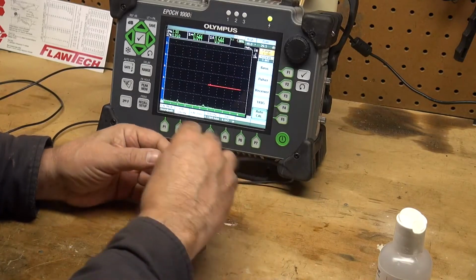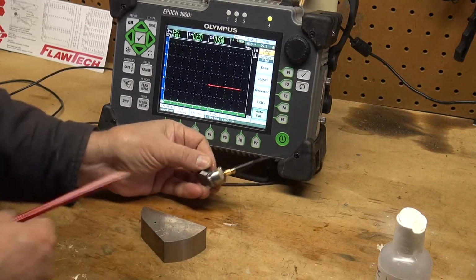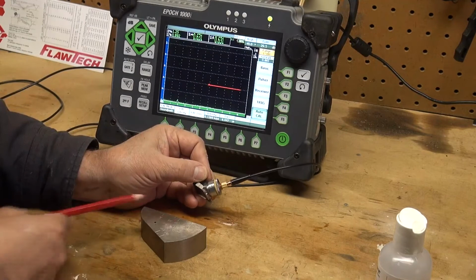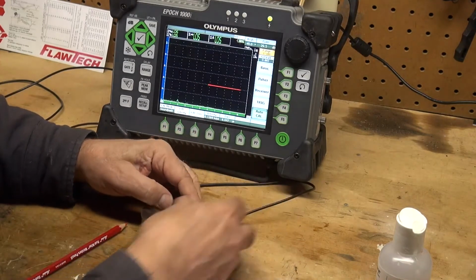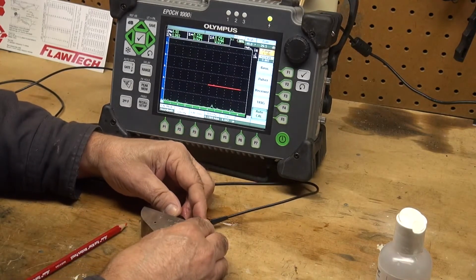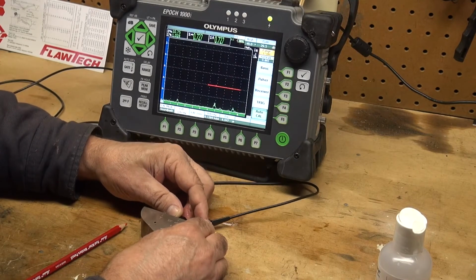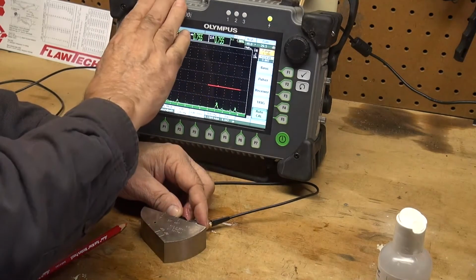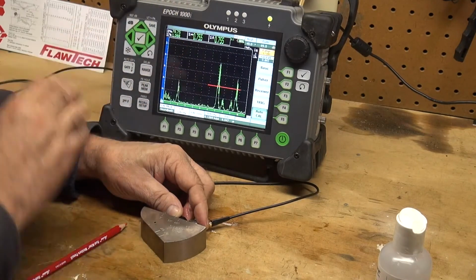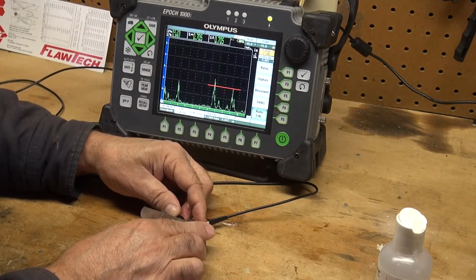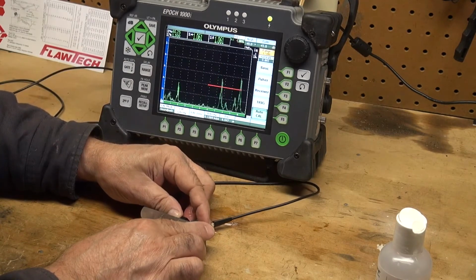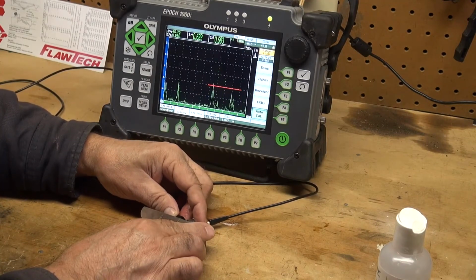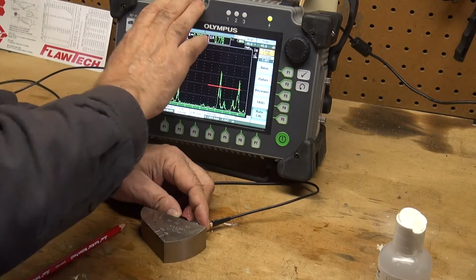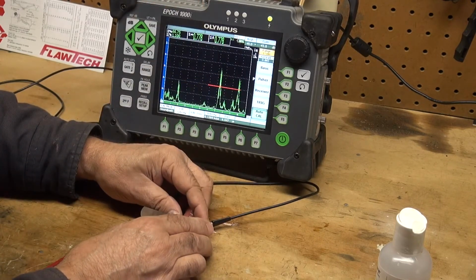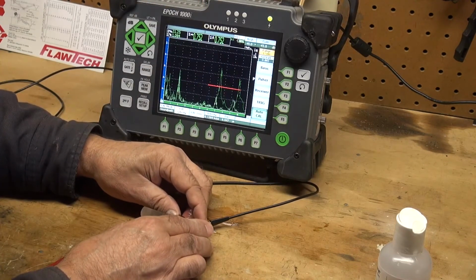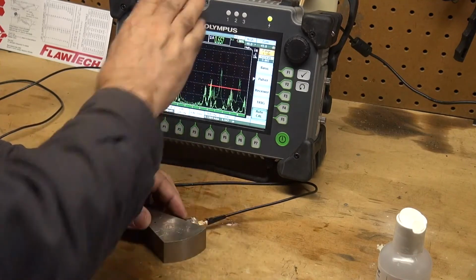So here's my beam index point. Here's the 45 beam index point, 45-degree angle. I'm going to put it right near there. I should see a reflector. And I do. I'm seeing a reflector right here. That guy coming up. Let me take him up to 80% full screen height. And there he is right there. That's the side drilled hole. So let me hit the peak memory. And I go back and forth. Whoops, I slipped. Peak memory.